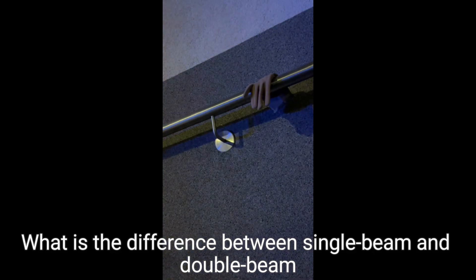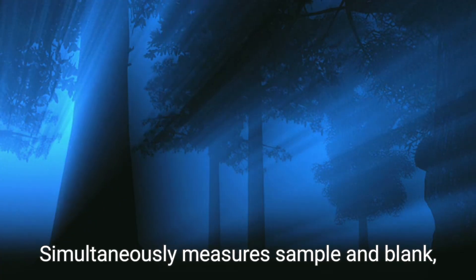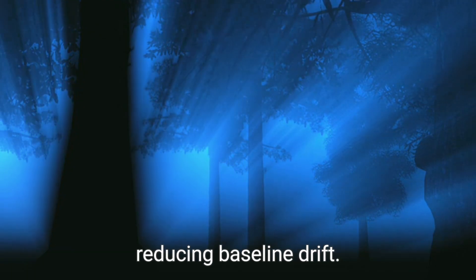What is the difference between single beam and double beam instruments? Single beam measures sample and blank separately. Double beam simultaneously measures sample and blank, reducing baseline drift.